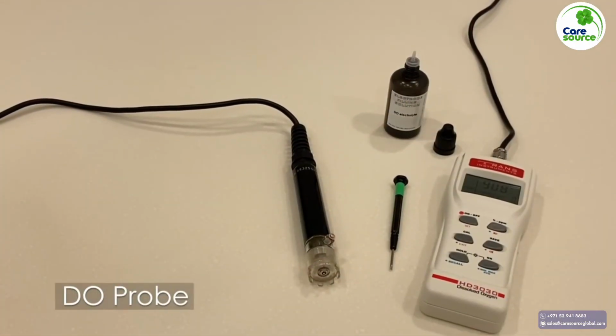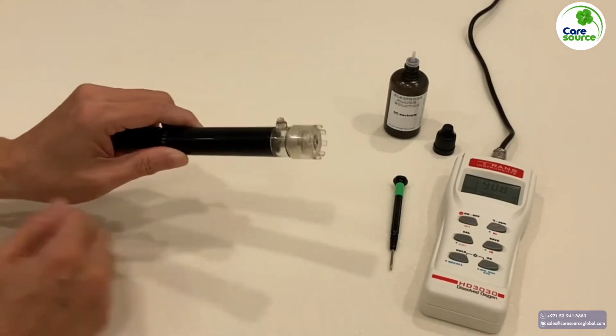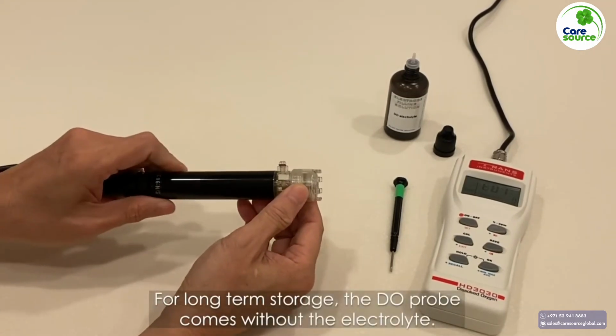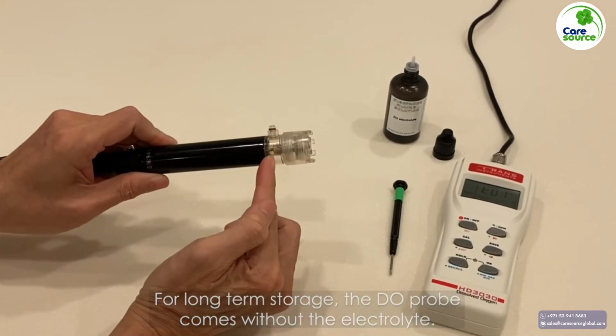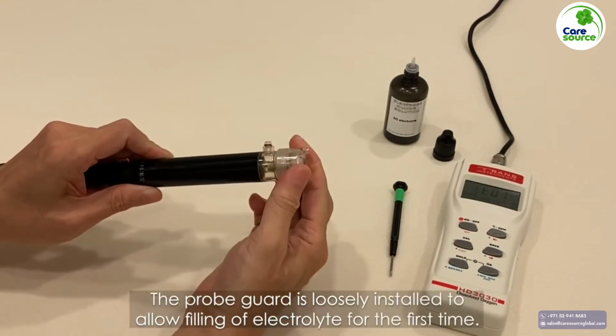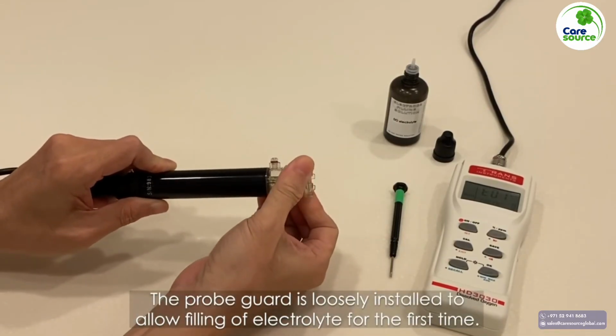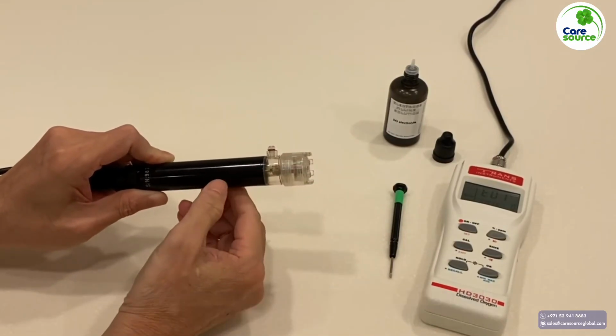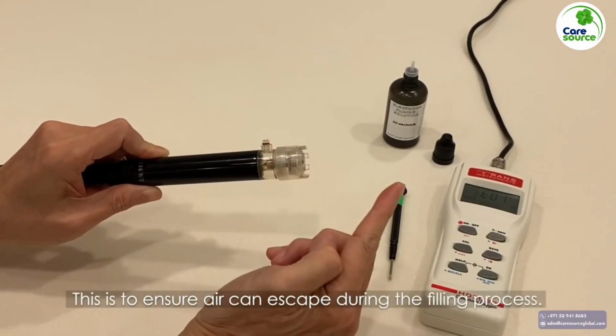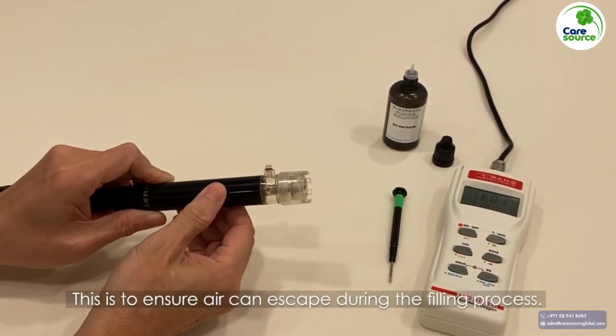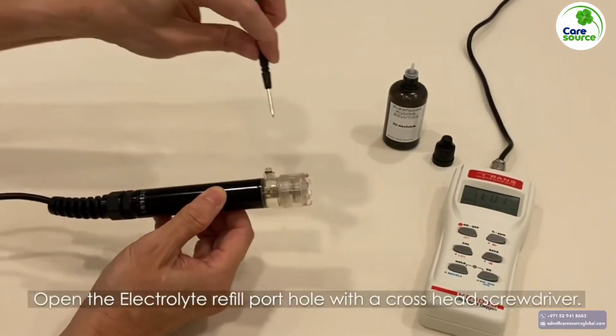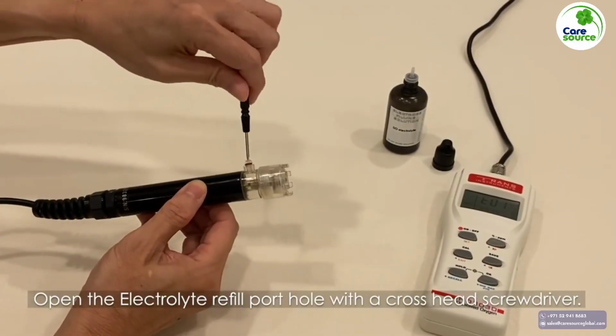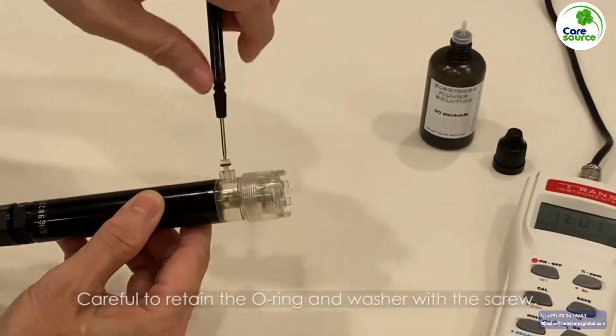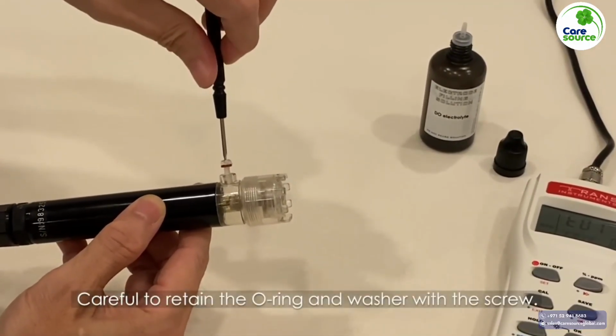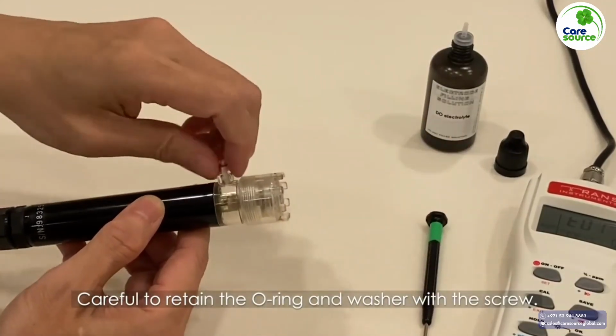Let us take a look at the DO probe. For long-term storage, the DO probe comes without the electrolyte. The probe guard is loosely installed to allow filling of the electrolyte for the first time. This is to ensure air can escape during the filling process. Open the electrolyte refill porthole with a crosshead screwdriver. Be careful with the retained O-ring and washer with the screw.